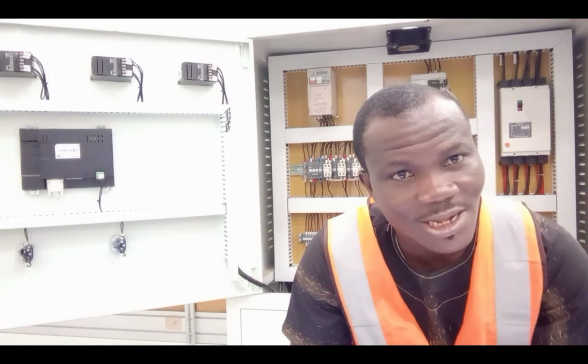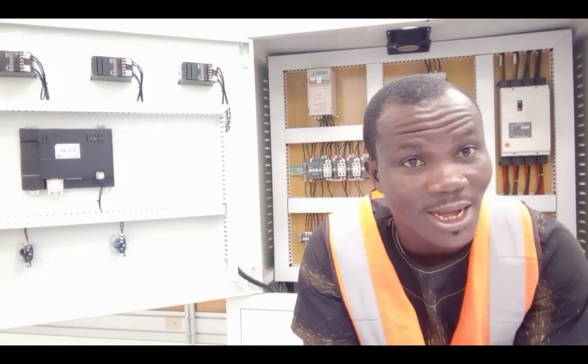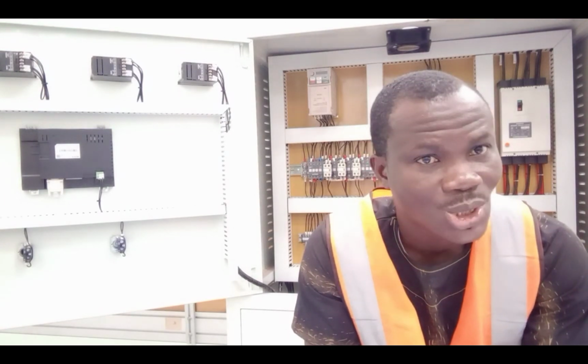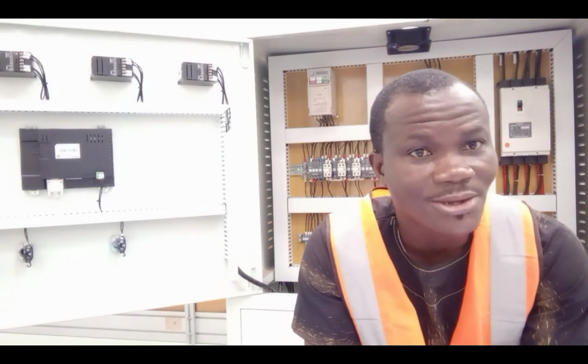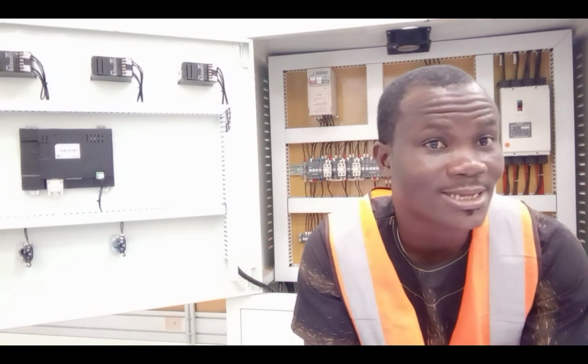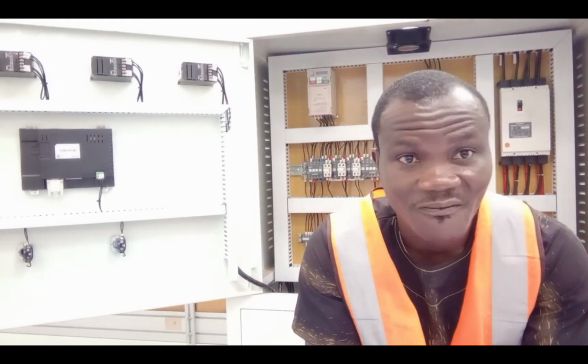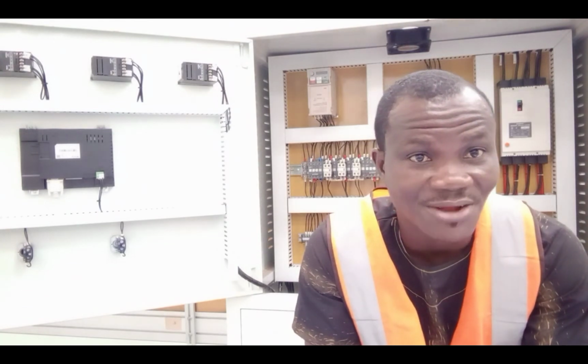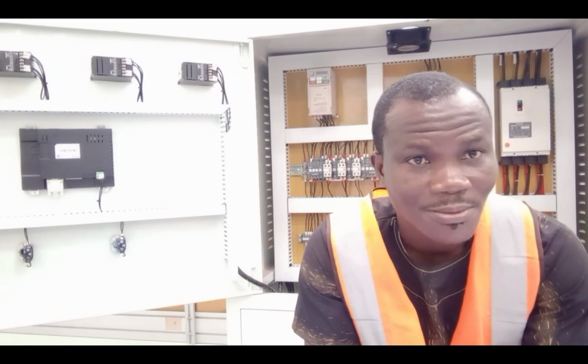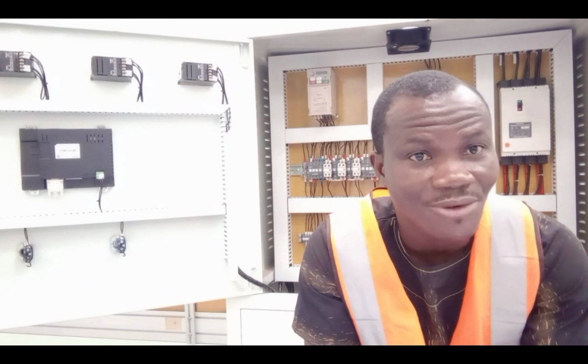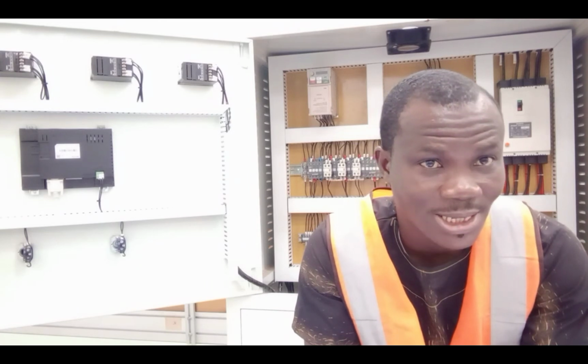Now, this current must not be more than the current capacity of the cables that are used to wire that cooker. So in this case, if we are using a wire that can carry up to 17 amps, looking at the factors around your wiring environment, then you can only select circuit breakers that have ratings below 17 amps.